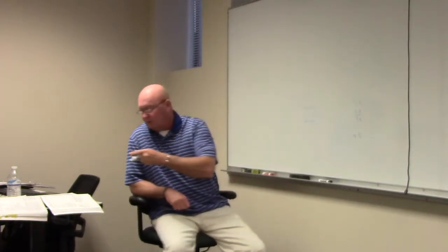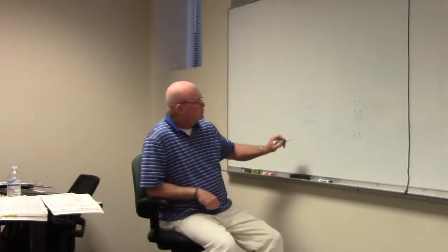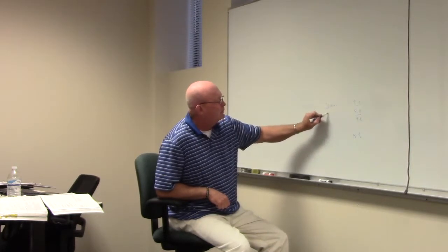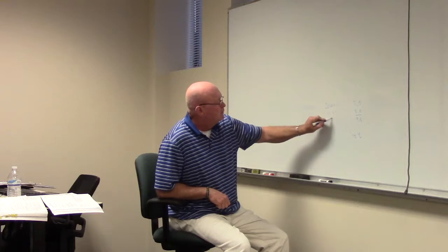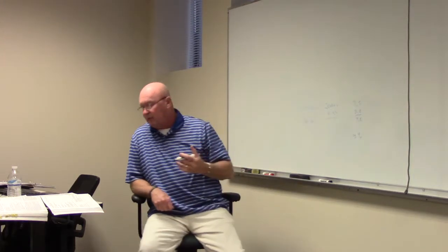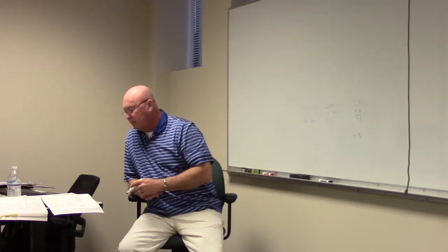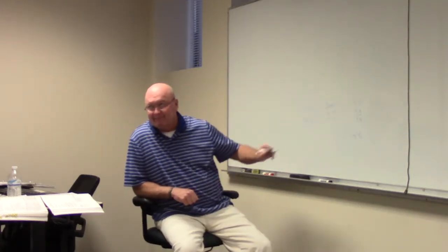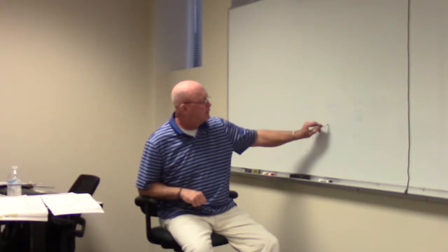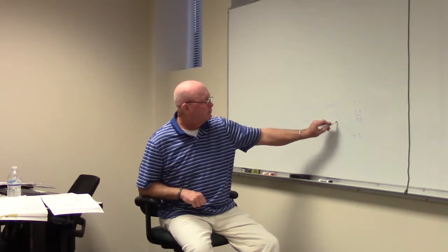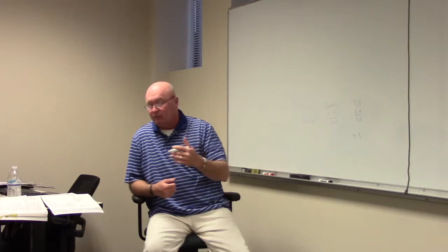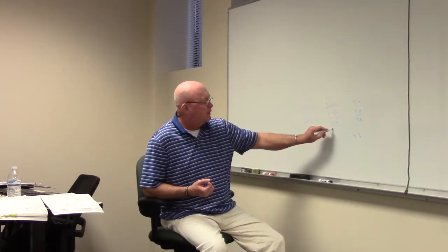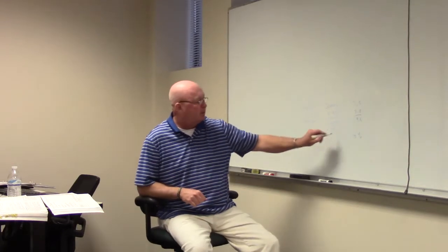And what they did next, they did the 200,000 times 4.5 VA. Let's do that math. I got 900,000. And then what we're going to do with that 900,000? Multiply it times 75%, right? How much is that equal to?